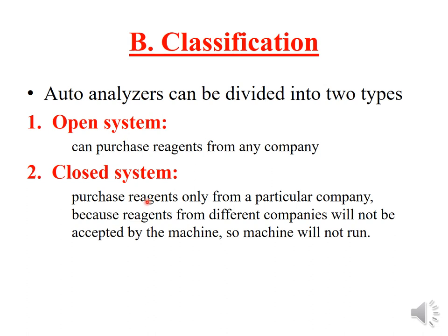For closed system auto-analyzers, the reagents have to be purchased from a particular company, and any other reagents will not be accepted by the equipment — the machine will not run the test. It is known as a closed system because only one brand of reagent can be used.